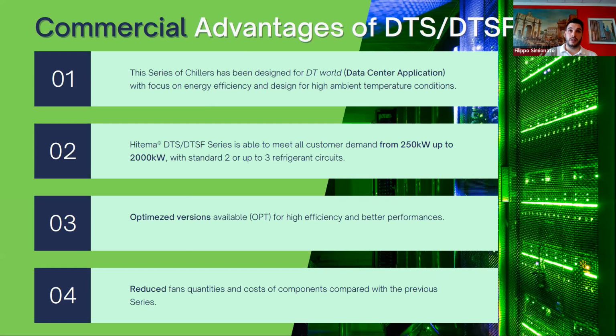So, giving the commercial department a wide range of opportunities, not only for the operating conditions, but also for the range of cooling capacity. With our range, we can meet from 250 kilowatts up to 2000 kilowatts of cooling capacity, designing with 2 or 3 refrigerant circuits. Now, for example, based on our philosophy and mentality of customization, we are designing a 4 refrigerant circuit unit in back-to-back configuration with 2 points of feed, working with 4 refrigerant circuits, and also staying within 30 meters of cabinet length.